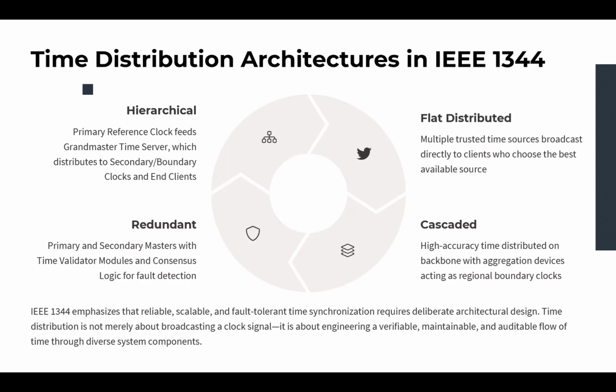The strength of this architecture is that it has very high accuracy. The monitoring and control is centralized, and we could easily validate and audit it. But it requires redundancy planning to avoid a single point of failure. Synchronization paths can also be asymmetric and should be calibrated constantly.